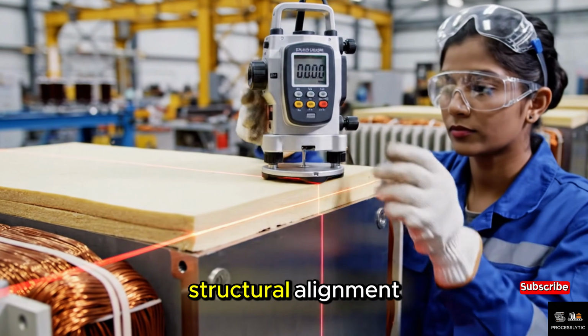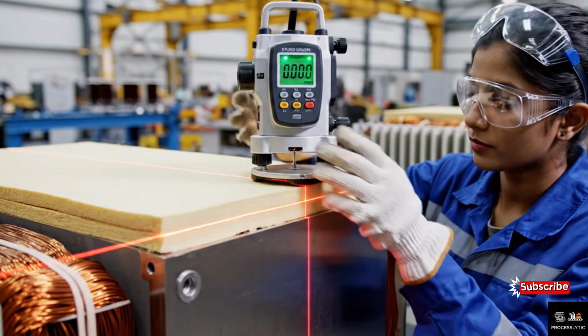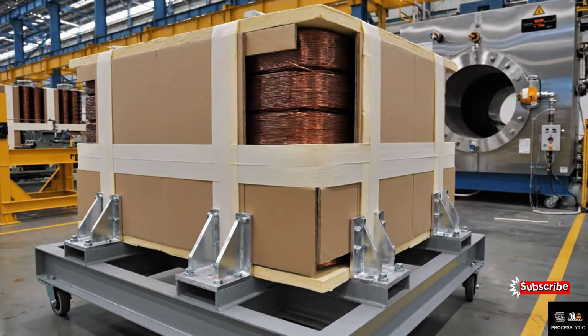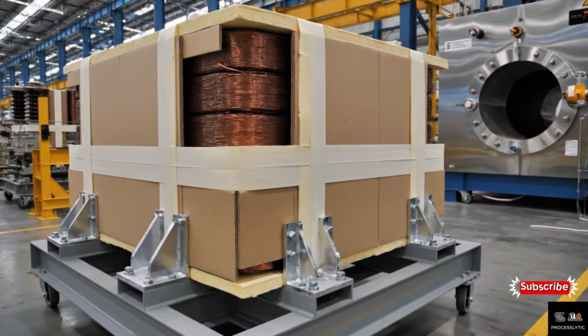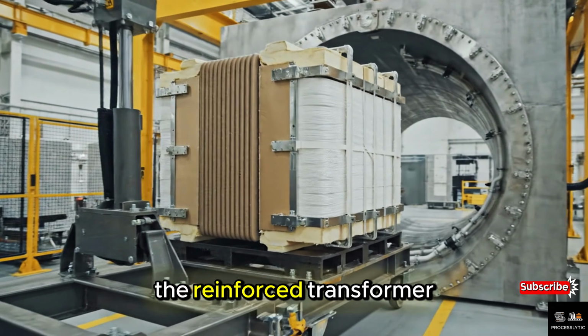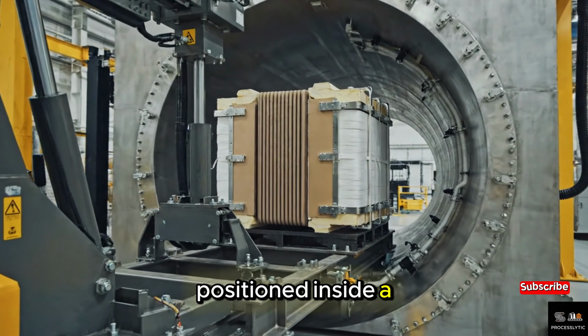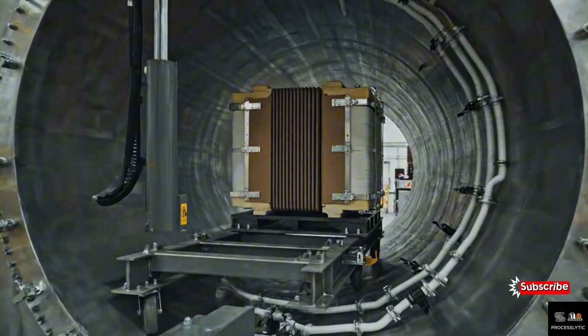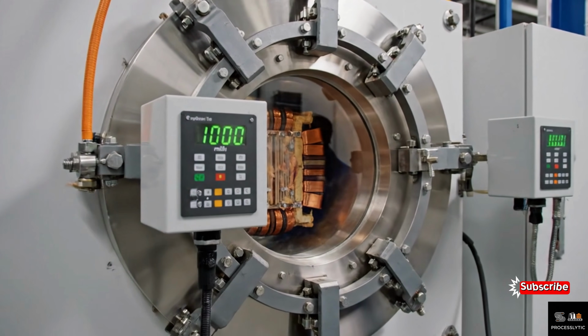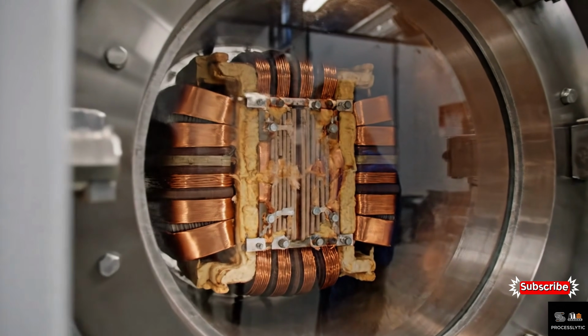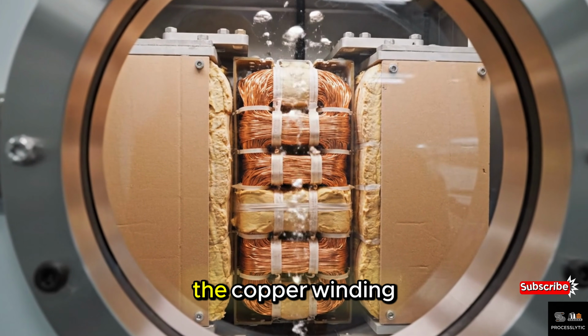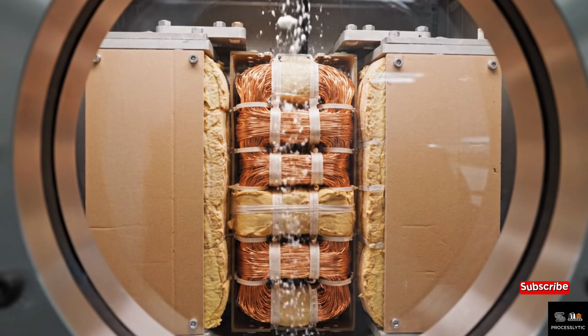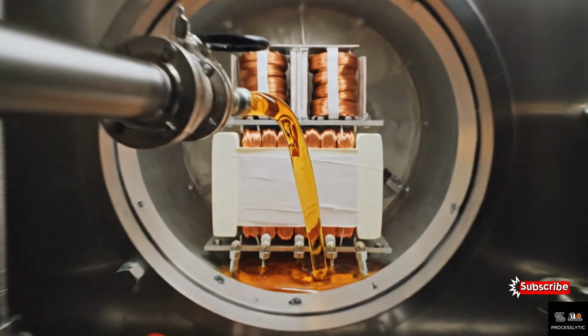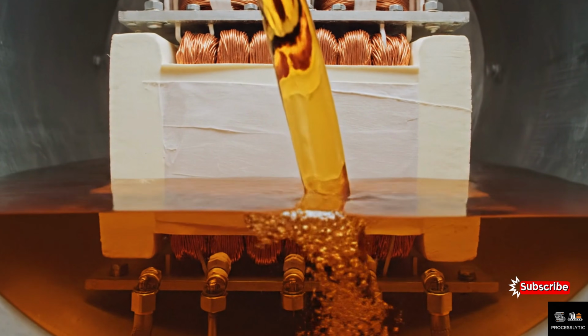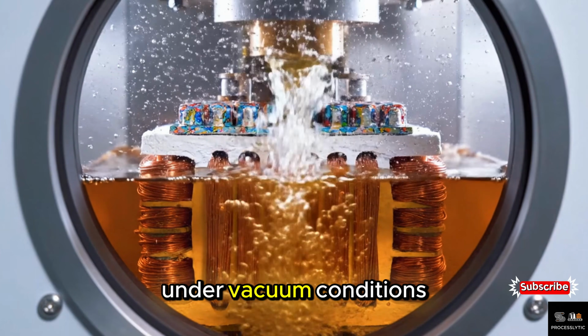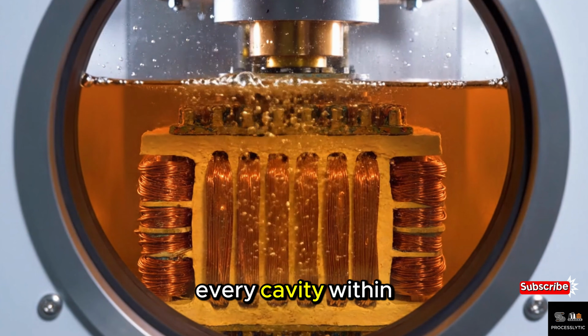Dimensional inspection ensures structural alignment before vacuum impregnation. The reinforced transformer coil assembly is positioned inside a sealed vacuum impregnation chamber. Vacuum pressure removes trapped air from the copper winding structure and insulation layers. Under vacuum conditions, the insulating resin penetrates every cavity within the winding structure.